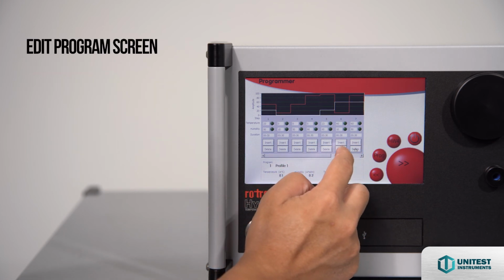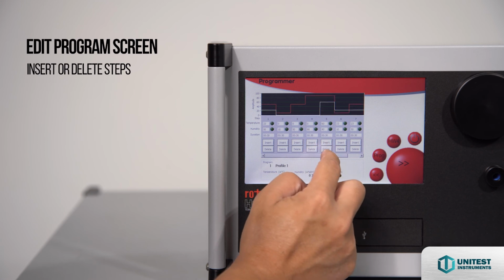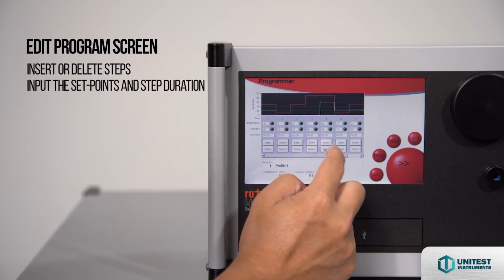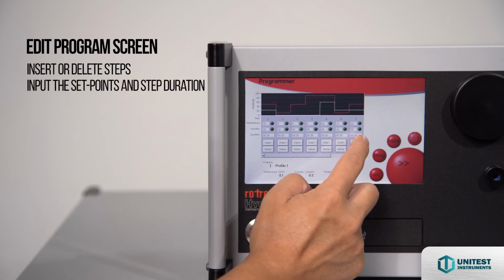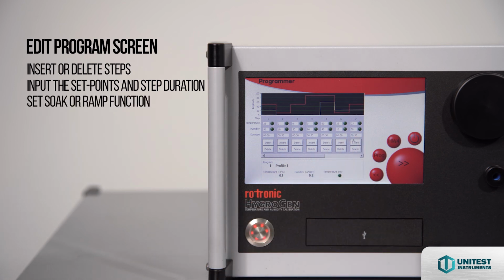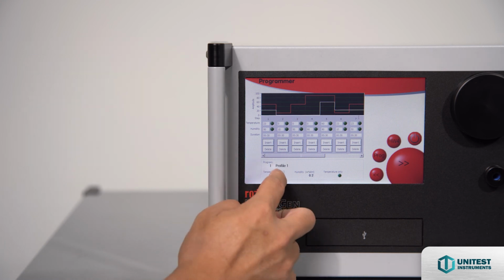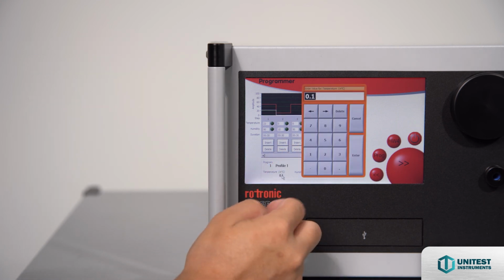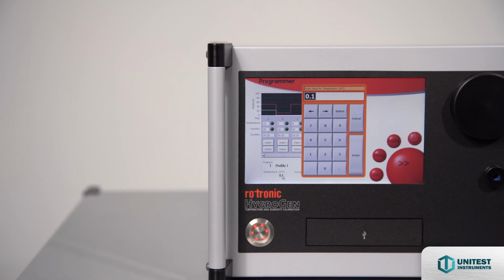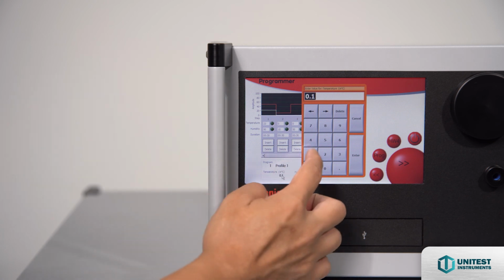On the edit program screen, you can insert or delete steps, input the set points and step durations, and tell HG2 whether that particular step is a soak or a ramp function. Each field can be modified by tapping or clicking on the number that is corresponding to a header, for example, tolerances or set points.